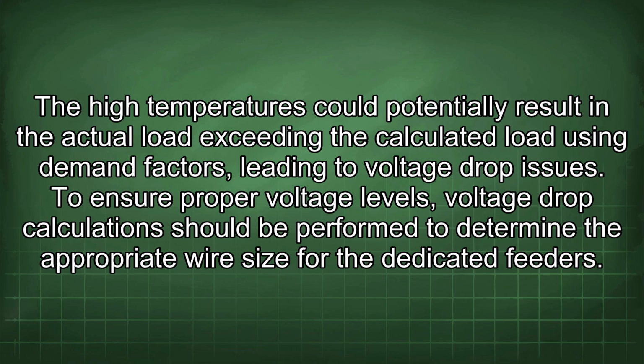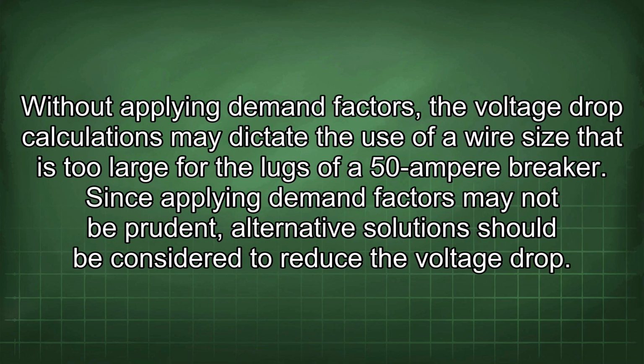drop issues. To ensure proper voltage levels, voltage drop calculations should be performed to determine the appropriate wire size for the dedicated feeders. Without applying demand factors, the voltage drop calculations may dictate the use of a wire size that is too large for the lugs of a 50 ampere breaker. Since applying demand factors may not be prudent, alternative solutions should be considered to reduce the voltage drop.